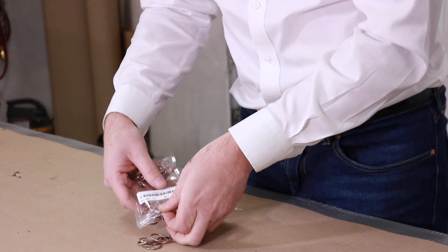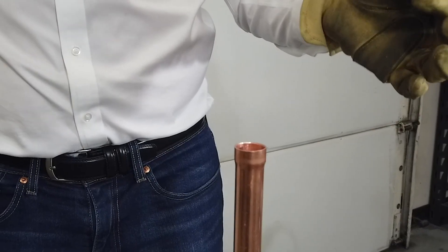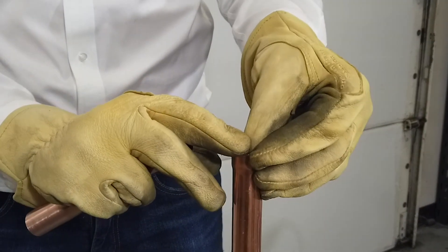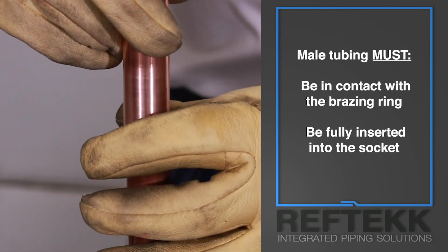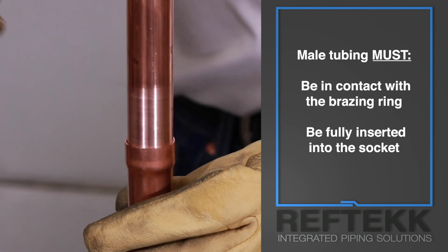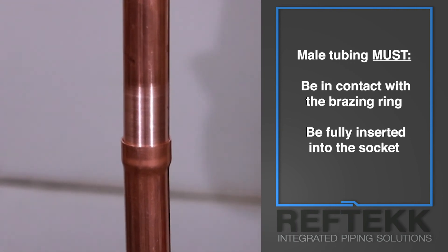Select the proper size brazing ring for the tubing you're brazing. Make sure the ring is shiny, silver-bronze in color, round, and has a gap between the ends with no obvious defects or abnormalities. Place the brazing ring into the end of the female socket — don't push it to the bottom with your finger, and if it won't fit square into the socket with a little gap, get another brazing ring. Now insert the male tube into the brazing socket and use it to push the brazing ring to the bottom of the socket. The male tube must stay in contact with the brazing ring for a successful brazing process.